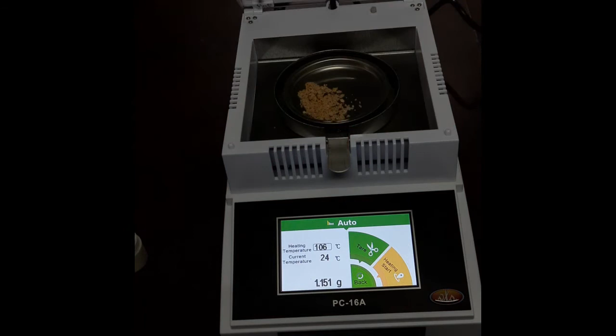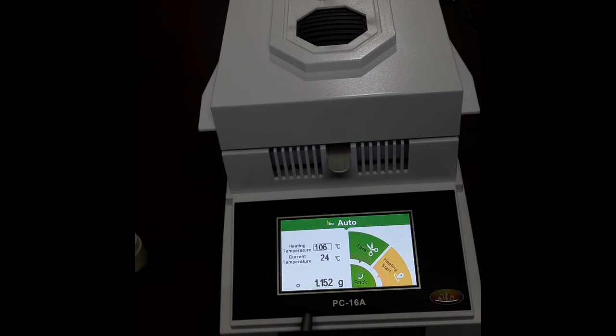After taking the sample, just spread it for uniformity. And close the lid. Whenever this stable symbol comes, press heating start. Now heating temperature required is 106 degrees. End mode is auto. Current temperature is 26. Now it has started heating. Now it will rise to 106, and how much time it takes will show here, and the moisture percentage live will show here.